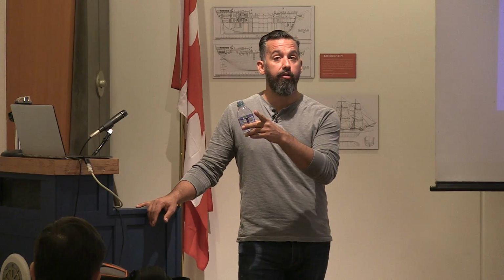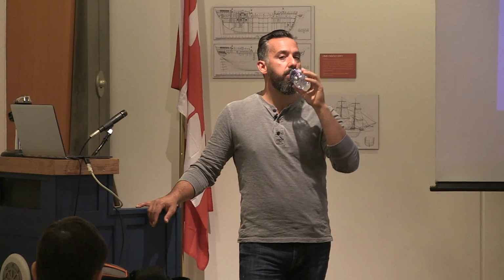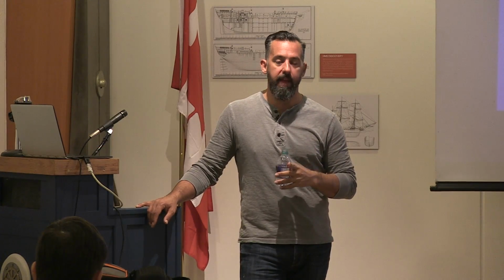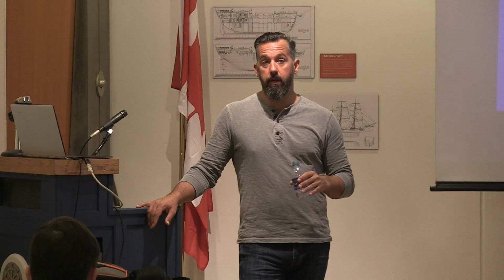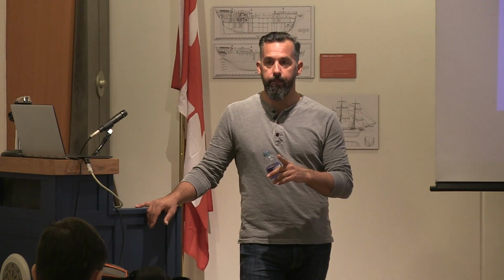And how do you turn your inverter off? That's a really good question, by the way. That's a trick question. If it's on charge only, like ours has a charge only setting, it is not on if it's on charge only, correct? Correct, yes. But what else do you do? Now think about what are the ramifications of not doing this properly. Well, if you turned off the master, we've got a master DC disconnect. Yeah. Most inverters don't have one.